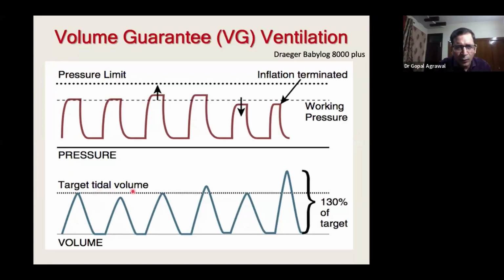If the actual tidal volume is less than the set tidal volume, the next breath it will increase the pressure, and it will again check the tidal volume delivered. If it reaches the set tidal volume, the next breath it will give the same pressure as the previous breath. Suppose in this breath the tidal volume is high, in the very next breath it will decrease the pressure. So it will keep on changing the pressure being delivered depending on the previous tidal volume. That's the key. So it's an automated regulated pressure delivery depending on previous tidal volume and pressure.